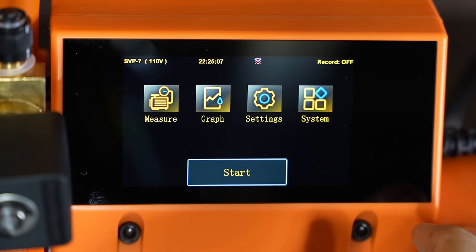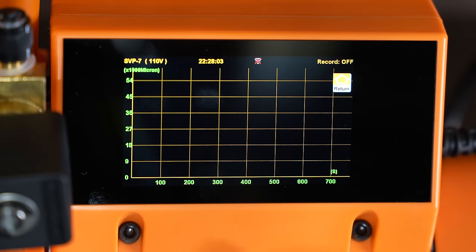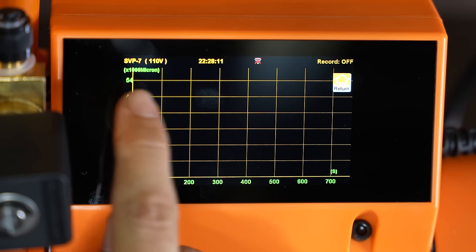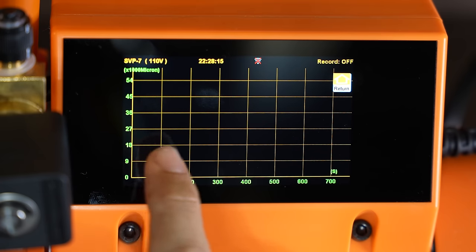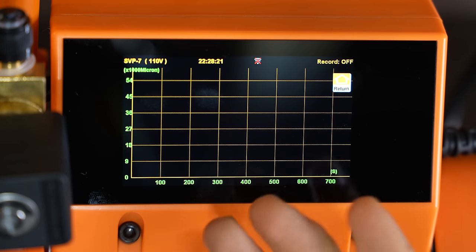Let's return back to home. The second icon is the graph. This just gives you a graph readout of the vacuum progress. So as the pump is running, the graph will go down depicting what the progress is like inside of the system that you're evacuating. This is in thousands — you got 54,000 microns, 45, 36, 27, and so on. And this axis is seconds. So the graph will go down as the pump is running.